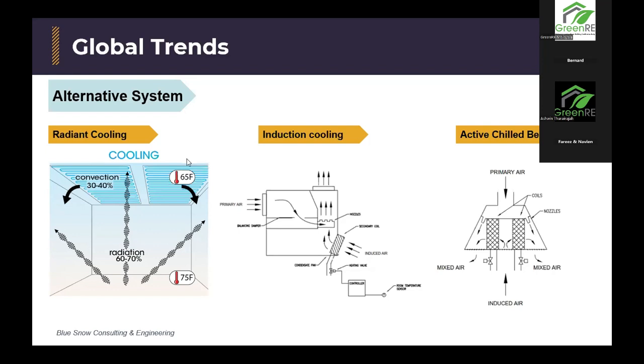The last one is active chill beams. It is a mixture of induction cooling and also radiant cooling. So if you mix induction and radiant cooling, you would get what is known as active chill beam. Active chill beams, in fact, in Blue Snow, we did one design back in 2013. It was able to get LEED Platinum. A lot of people tend to say the systems are not feasible in Malaysia. Again, I don't see why it's not feasible when I know buildings that have it and can do it. Even the Prime Minister's office uses active chill beams.